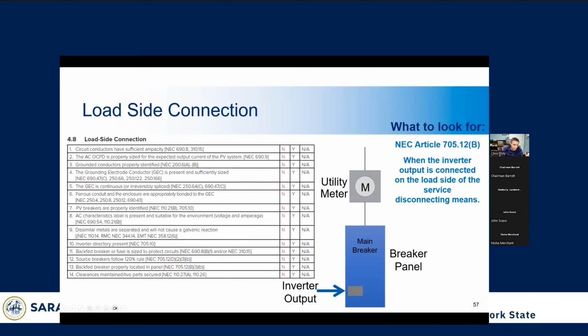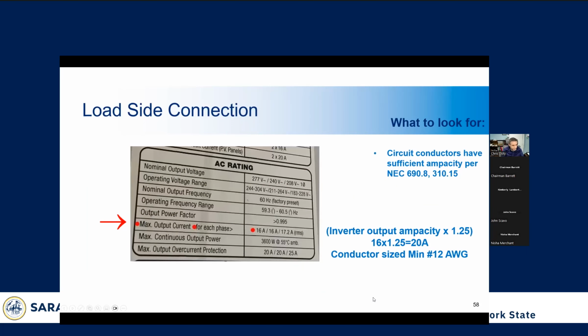And so if you have a bus bar that is rated at higher than 100% of the utility meter or the main breaker rating, you should be able to locate this backfeed breaker anywhere within the panel. So when you're looking at the load side connection, you need to look for your circuit ampacity. That's the amount of amperage that the circuit can carry.